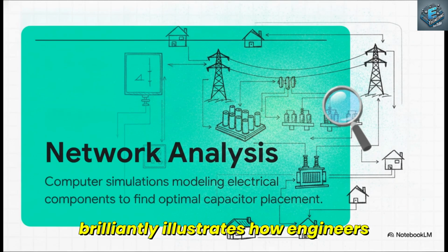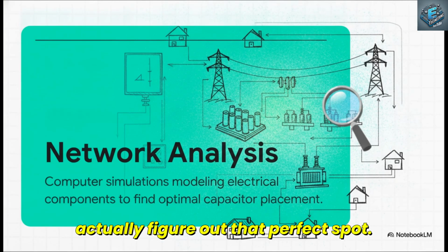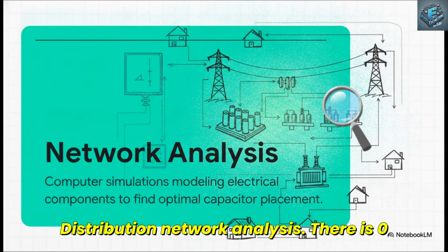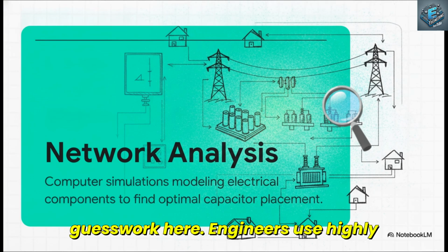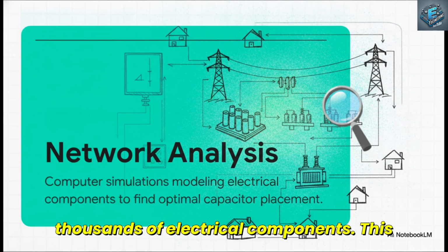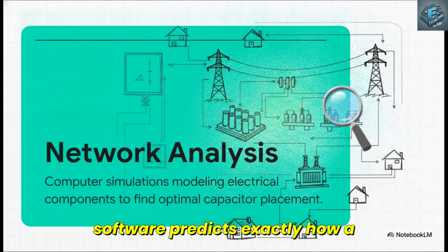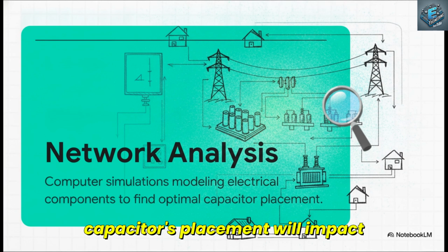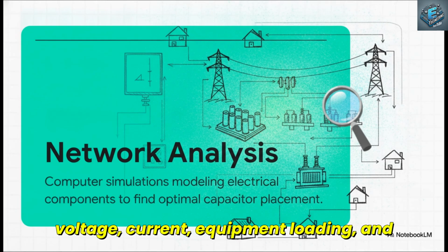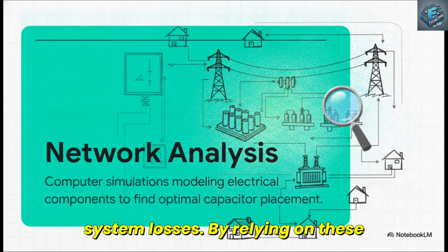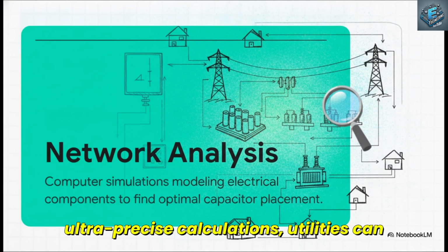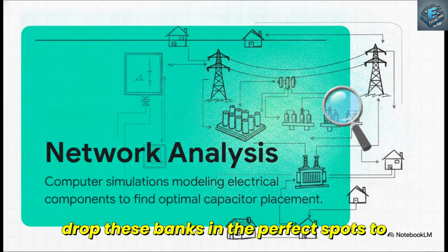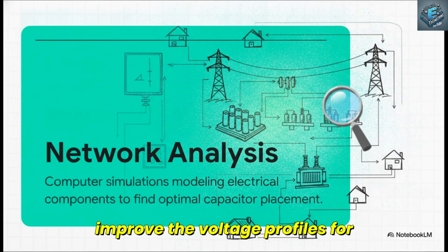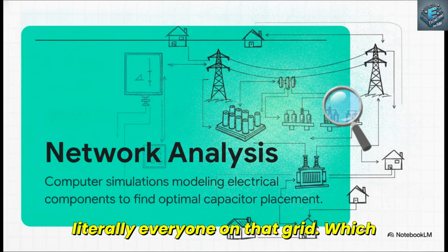And this brilliantly illustrates how engineers actually figure out that perfect spot. Distribution network analysis. There is zero guesswork here. Engineers use highly detailed computer simulations that model thousands of electrical components. This software predicts exactly how a capacitor's placement will impact voltage, current, equipment loading, and system losses. By relying on these ultra-precise calculations, utilities can drop these banks in the perfect spots to dramatically lower power losses and improve the voltage profiles for literally everyone on that grid.